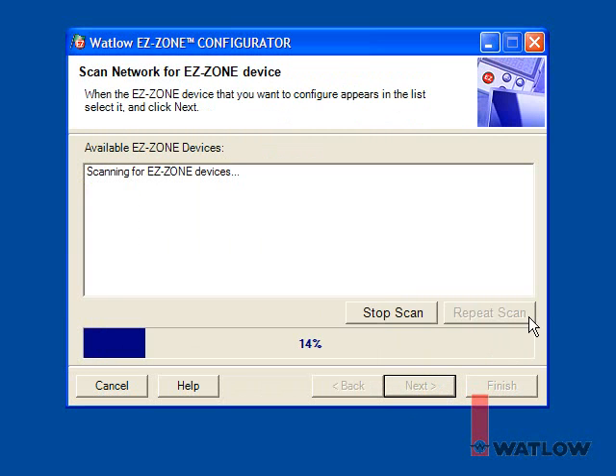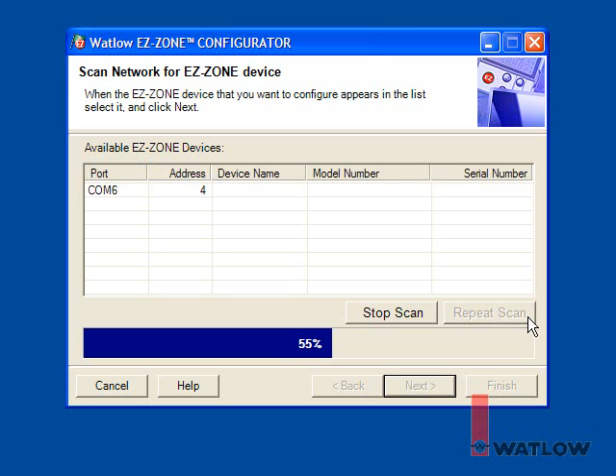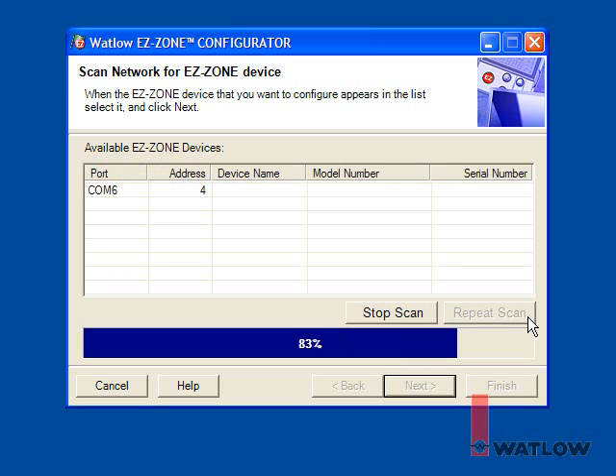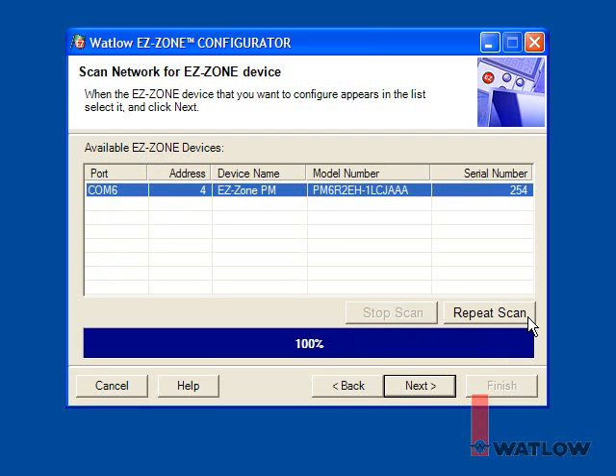If EZ-ZONE Configurator can't find the COM port, you may have to acknowledge an error message and try again. If it cannot find a controller, check the items listed on the screen, then click Repeat Scan. Once one or more controllers are found, EZ-ZONE Configurator displays a list of the found devices. That confirms that it is communicating and shows we have successfully installed the USB to 485 converter and correctly connected and configured the controller.